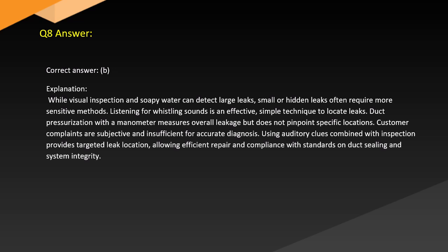Duct pressurization with a manometer measures overall leakage but does not pinpoint specific locations. Customer complaints are subjective and insufficient for accurate diagnosis. Using auditory clues combined with inspection provides targeted leak location, allowing efficient repair in compliance with standards on duct sealing and system integrity.